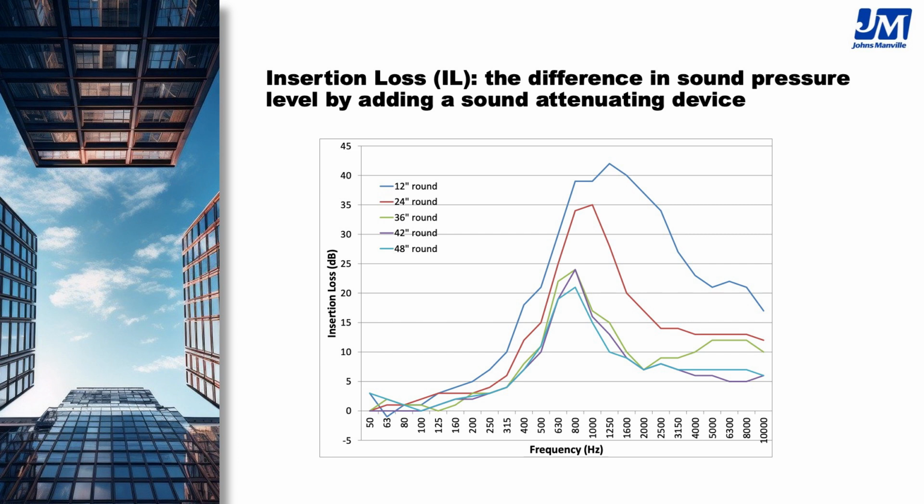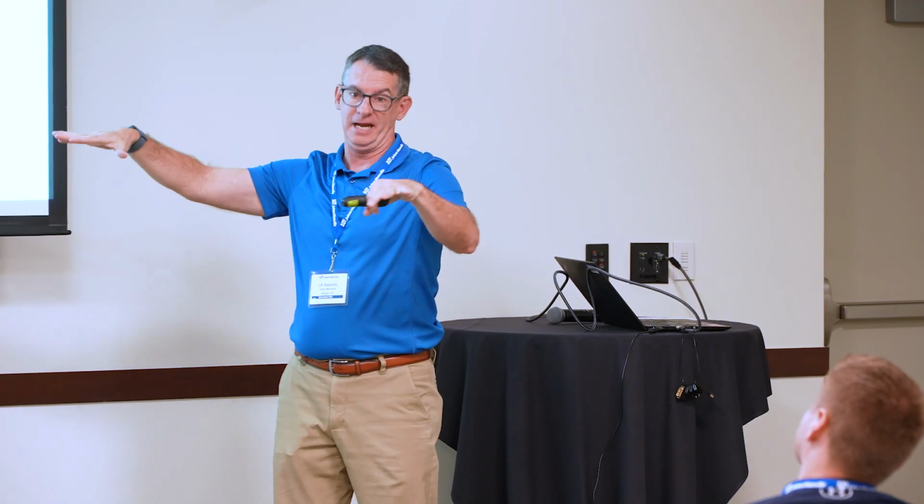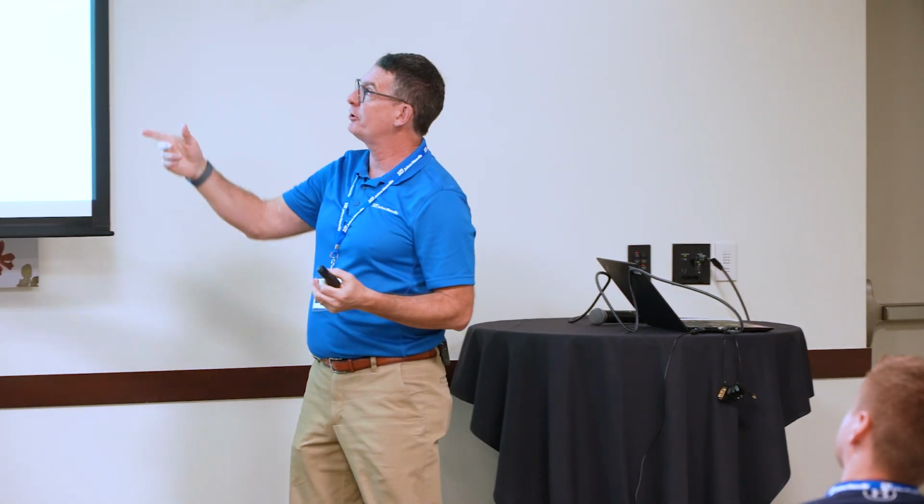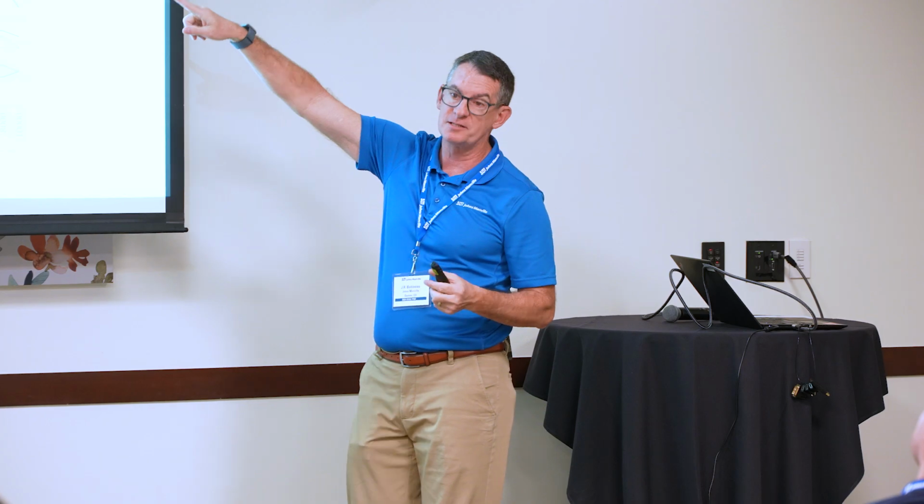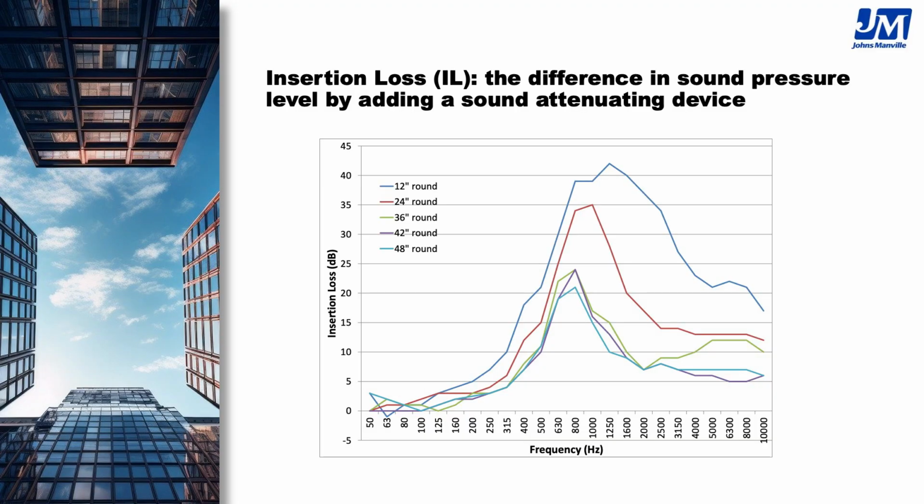One thing I did want to touch on, because in HVAC in particular, we publish things like sound absorption for materials, but at the end of the day, in the actual building, what really ends up mattering is what's called insertion loss. That's what a mechanical engineer designing a system is actually trying to get to.